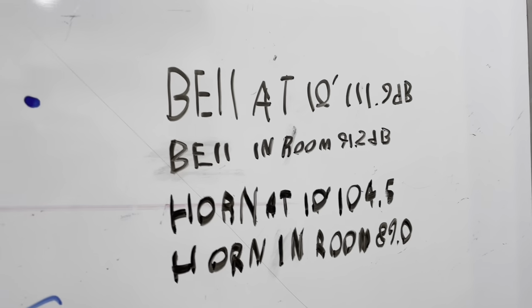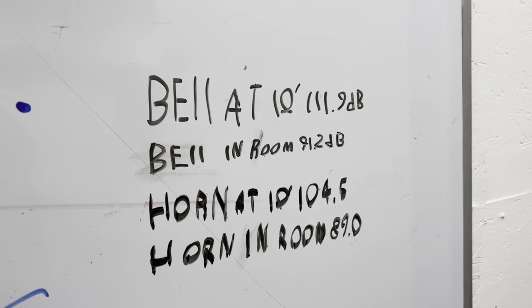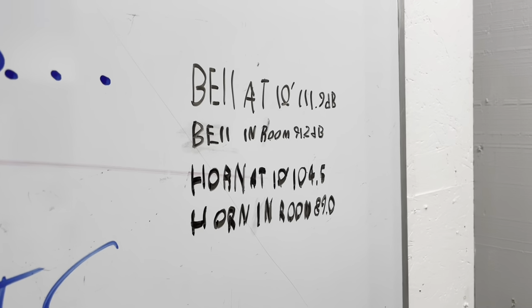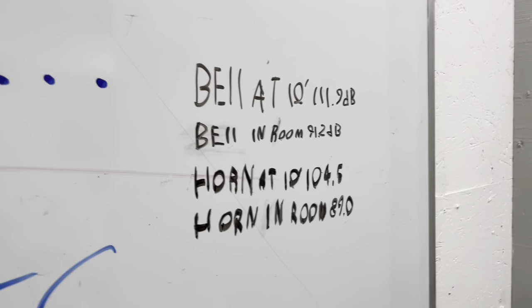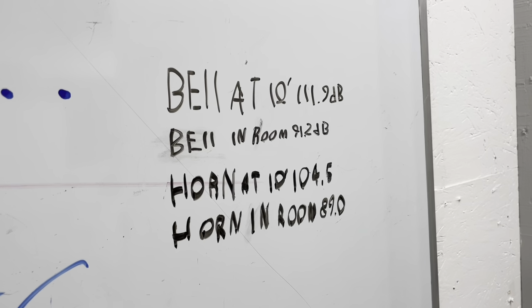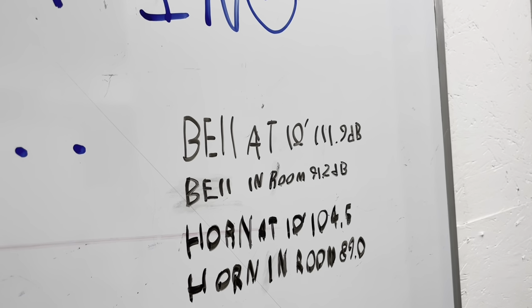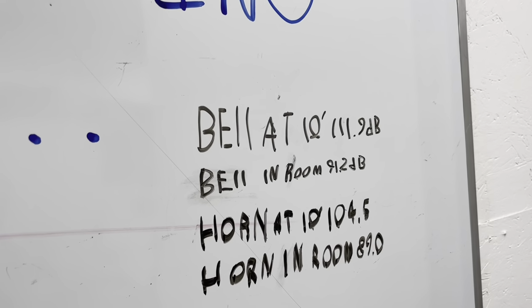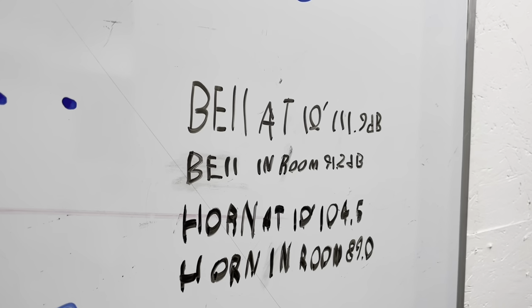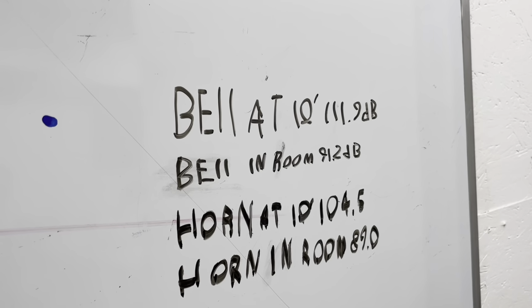Well, those are our results. So as far as volume test, which was really the last test or pros or cons that I had to say about this, then I guess the bell wins. So I've mentioned quite a few pros and quite a few cons for each device. So I'm really gonna leave it up to you guys. I think the number one con for horn strobes is that they're not taken seriously and they don't come across as very urgent or important, and or they're just not understood or known what they mean because they're a relatively new technology. I think that's the biggest con for them, which is completely overlooked, as it's not really a fault on paper. It's just something to do with people and how they interpret it.